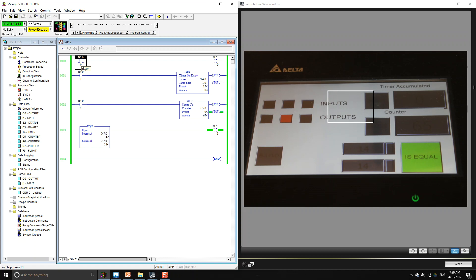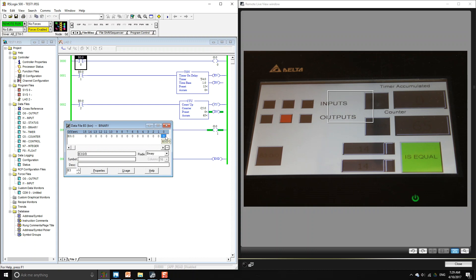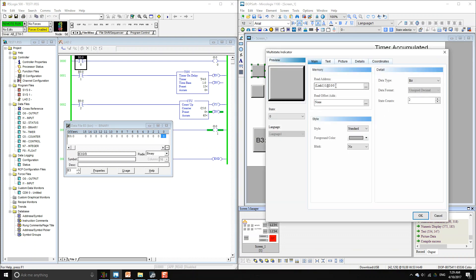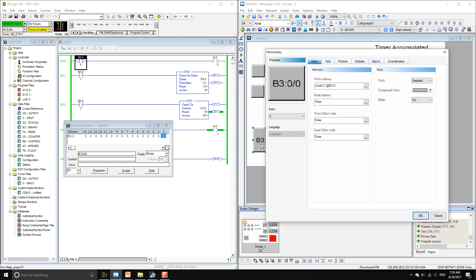To get the right address, for instance this contactor is at address B:0. You can go to Binary and get the address from there. It shows that the address is B3:0/0. On our HMI you don't have to specify it as B3 — you can just use plainly the letter B semicolon, then the word number, then a dash for the specific bit.